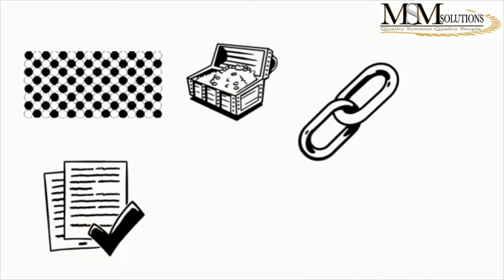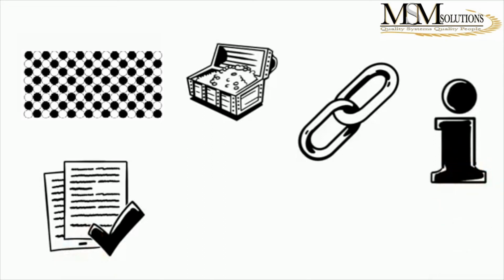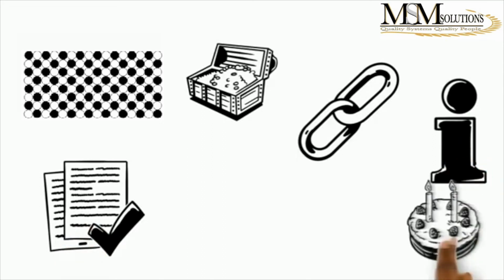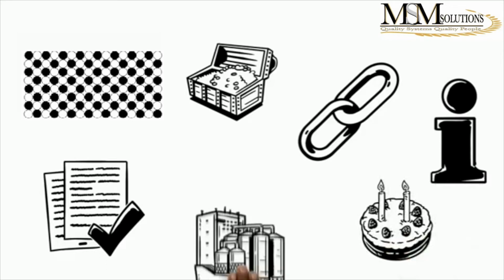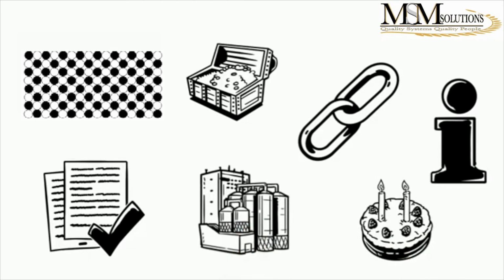Documentation, once you've got all this information, you need to document it well, such that if you're going to be using it for a year, for 2 years, 10 years, that everybody knows exactly how it was prepared, how it needs to be stored, and what needs to happen to it, and what value has been assigned to it, and how that number came about. And storage, does the storage get affected by opening and closing? How long once you've opened it you can store it, or if it's sealed, how long. So all of that is included, and it will give you a step-by-step guide on exactly how to do this.